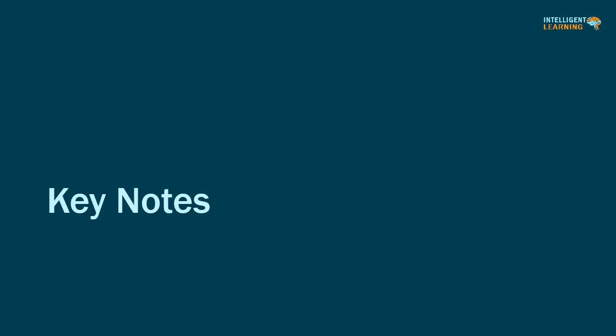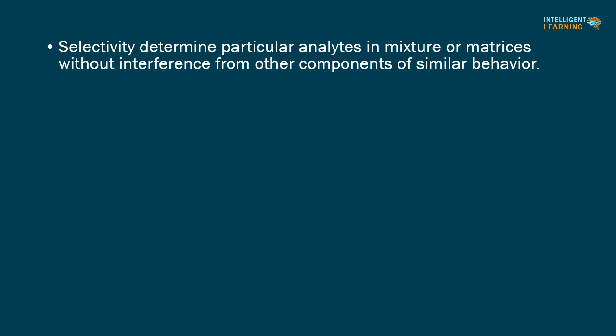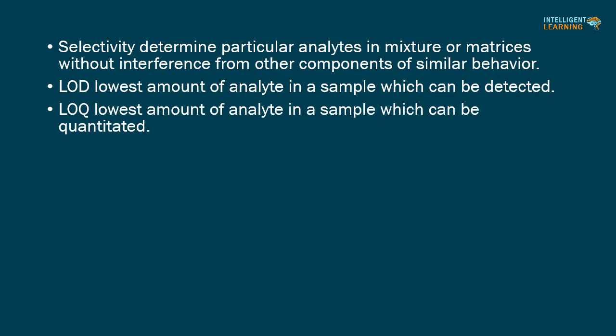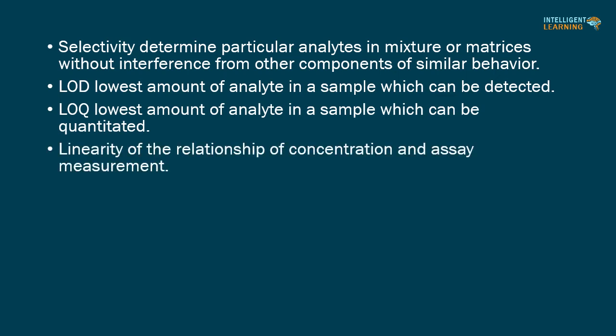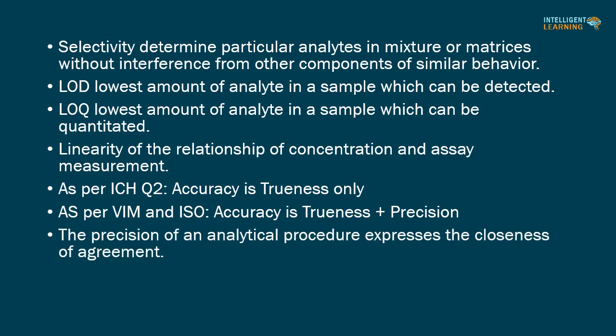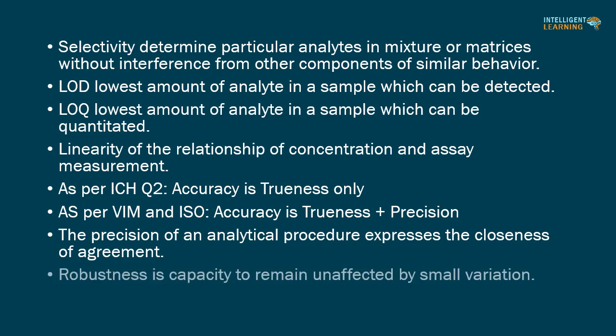Keynotes of this video: Selectivity — determines particular analytes in a mixture or matrix without interference from other components of similar behavior. LOD — lowest amount of analyte in a sample which can be detected. LOQ — lowest amount of analyte in a sample which can be quantitated. Linearity — the relationship between concentration and assay measurement. As per ICH Q2, accuracy is trueness only; as per VIM and ISO, accuracy is trueness plus precision. Precision expresses the closeness of agreement. Robustness is the capacity to remain unaffected by small variations.